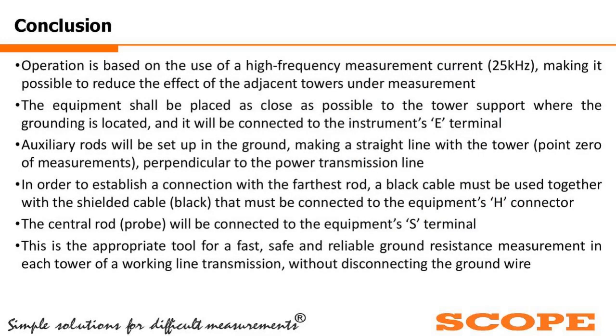So in conclusion, the operation is based on the use of a high frequency measurement current, which is generally in the range of 25 kilohertz, making it possible to reduce the effect of the adjacent towers under measurement. The equipment shall be placed as close as possible to the tower support where the grounding is located, and it will be connected to the instrument's E terminal. Means the instrument will be as near as possible to the tower. Auxiliary rods will be set up in the ground, making a straight line with the tower, with point 0 of measurement perpendicular to the power transmission line in order to minimize the effect of coupling.